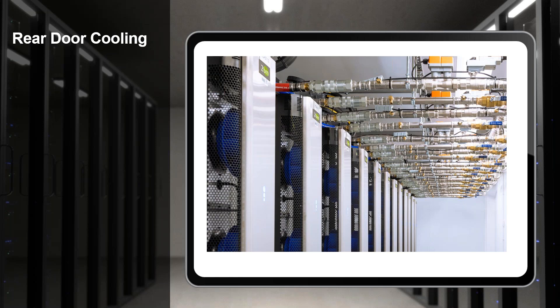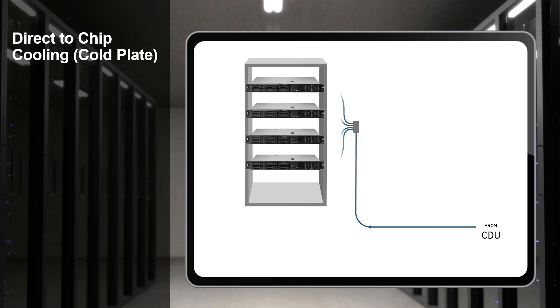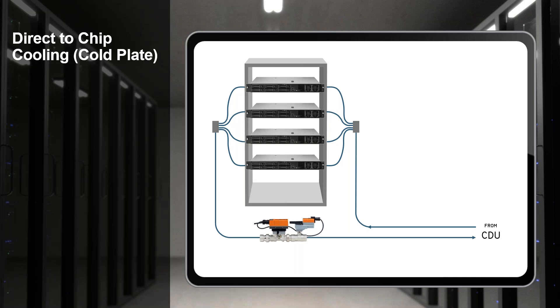What about direct-to-chip cooling, sometimes known as cold plate? Cold plates are a series of little heat exchangers that sit on top of the actual server chips inside these server banks. We're going to run cool fluid through them to pull the heat right off those processor chips. Each one of these servers in this rack is going to need a very specific amount of flow rate, and we can utilize this type of valve to make sure that we maintain the exact flows we're looking for and have the perfect heat exchange through there.